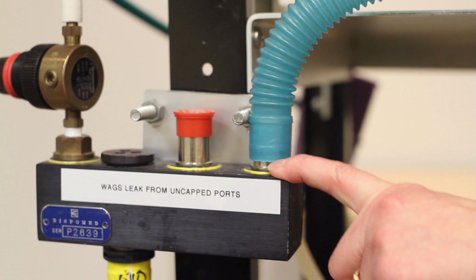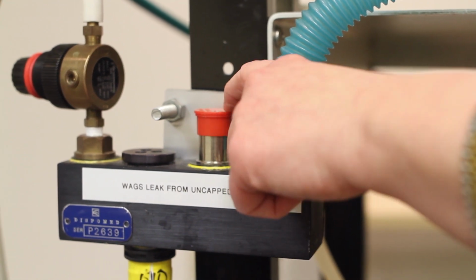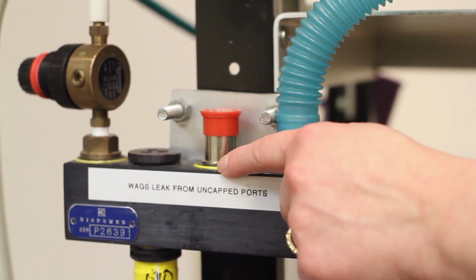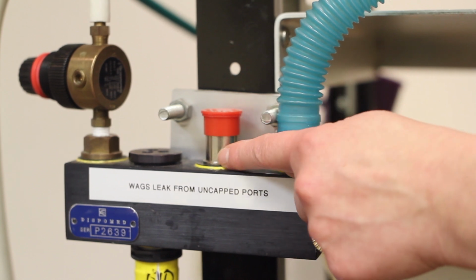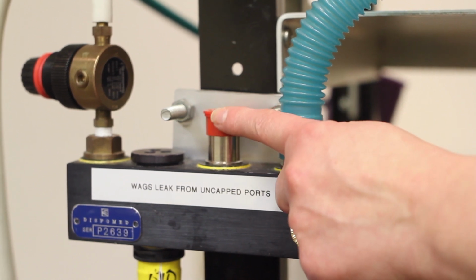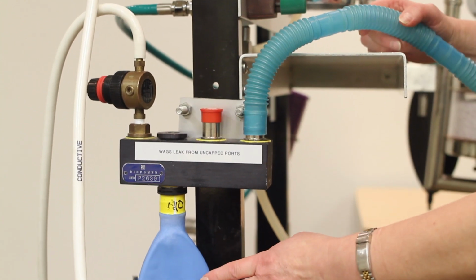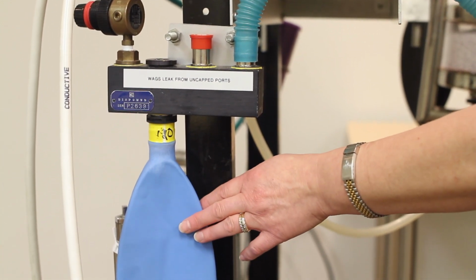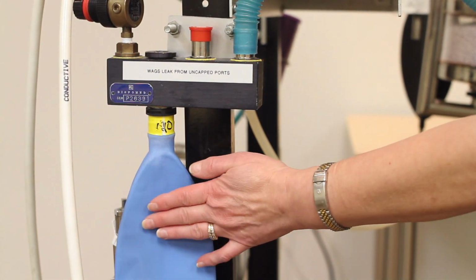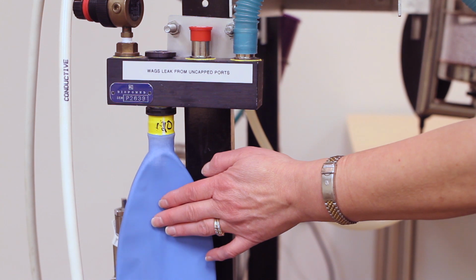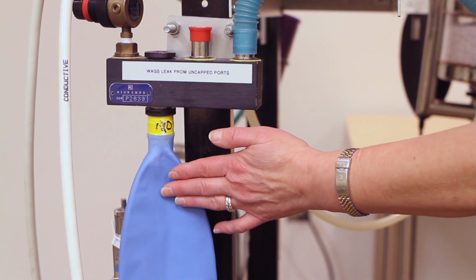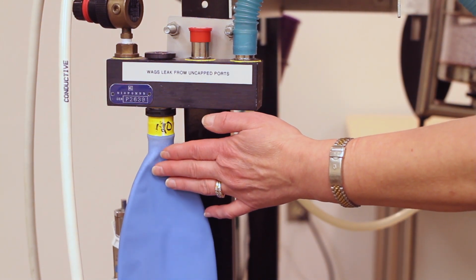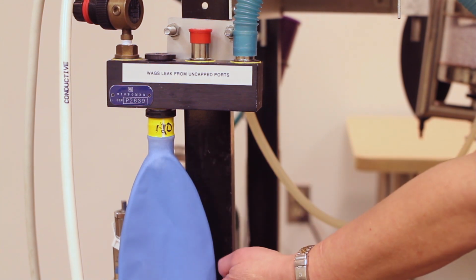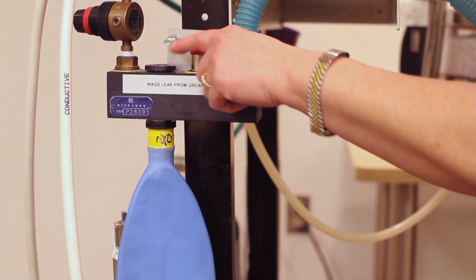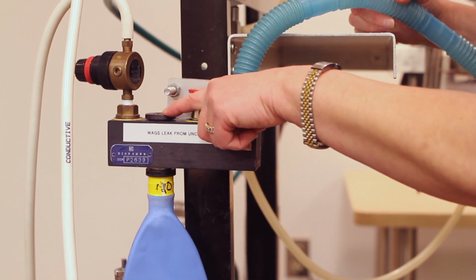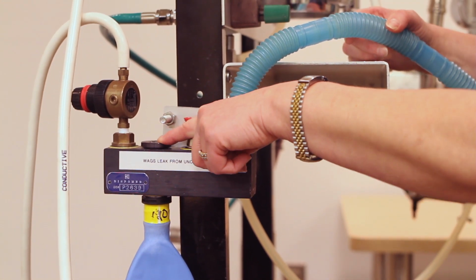You always want to make sure that your open ports are covered with this red cap, as open ports will allow waste anesthetic gases to come into your room. And you always want to make sure when you're emptying your rebreathing bag that you watch this WAG bag as well to make sure that it does not get overly distended, since once this bag gets completely full, the waste anesthetic gases will come out of the holes on top of this interface and come right back into the room.